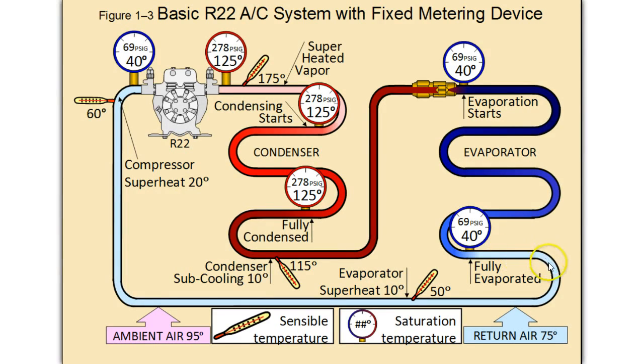Picking up superheat ensures that we have 100% vapor entering the compressor. At the tail end of the evaporator it picks up superheat, raising the sensible heat and the temperature of the refrigerant as it moves through the refrigeration line and back to the compressor as low-temperature, low-pressure superheated vapor. It is compressed in the compressor and the cycle begins again.